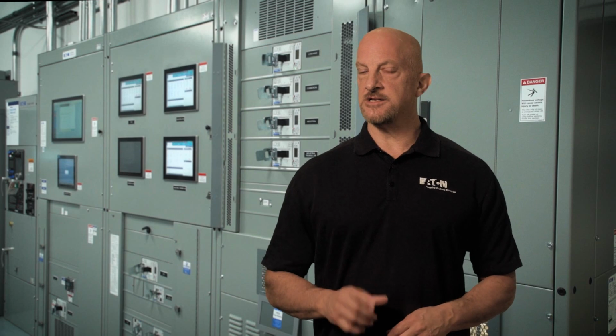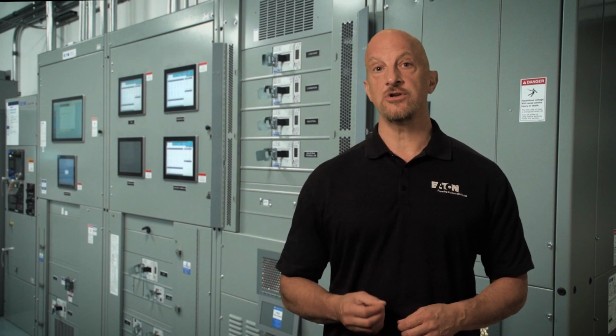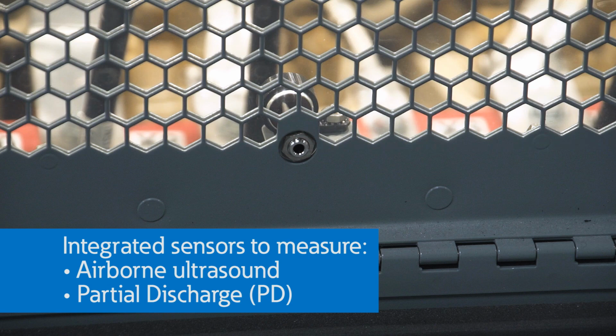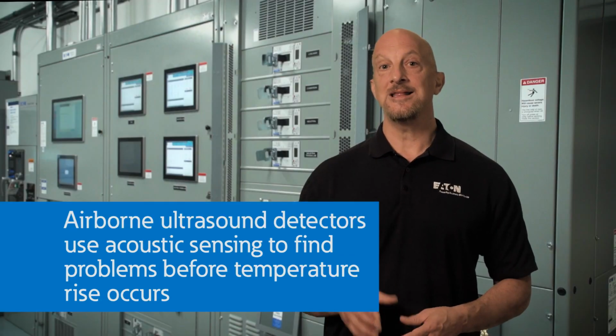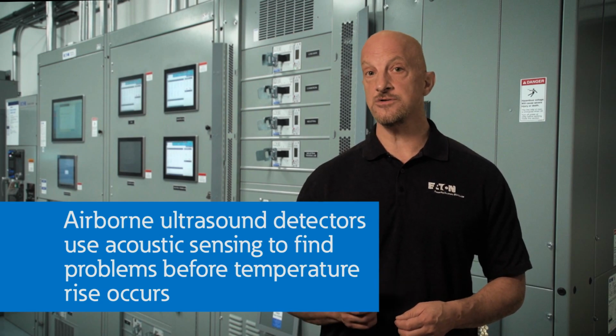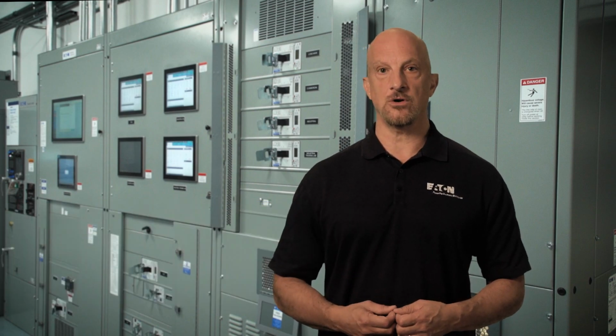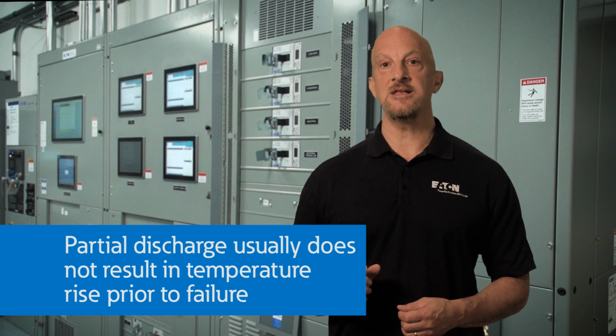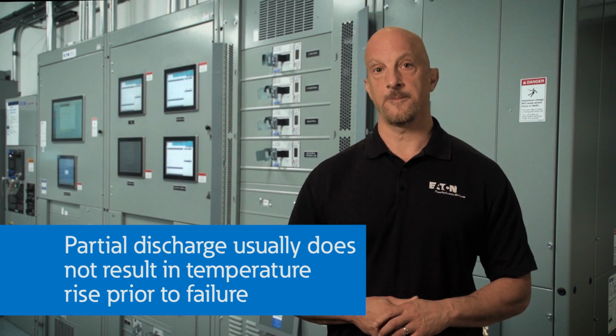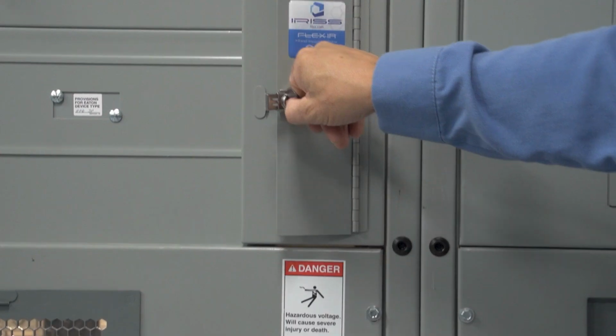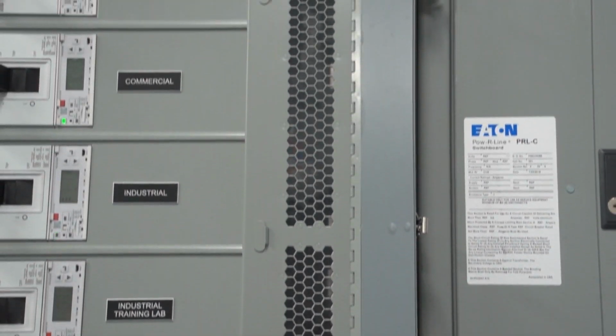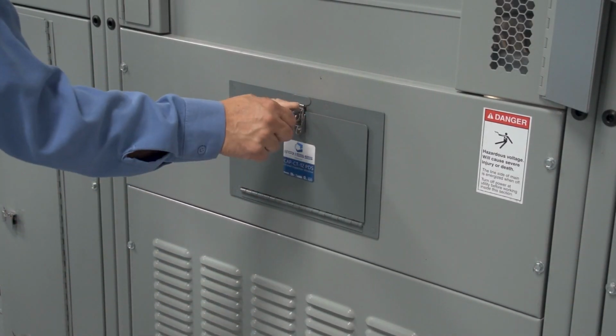Finally, while you're making the investment in this solution, we highly recommend that the construction of the window should have integrated sensor options available to measure airborne ultrasound and partial discharge, and should be compatible with the major brands of handheld testers available today. These testers can detect electrical faults and conditions acoustically when they first emerge and before temperature rises occur. And partial discharge faults are likely to never issue a temperature rise ahead of the equipment failing. A properly designed IR window or panel should, from its single installed point of access on the gear's compartment cover, enable all of these critical energized inspections to be performed while maintaining the energized compartment in a closed and guarded condition while the gear is operating and under load. All of this, as an example, is what you see mounted here on display at the PSEC.